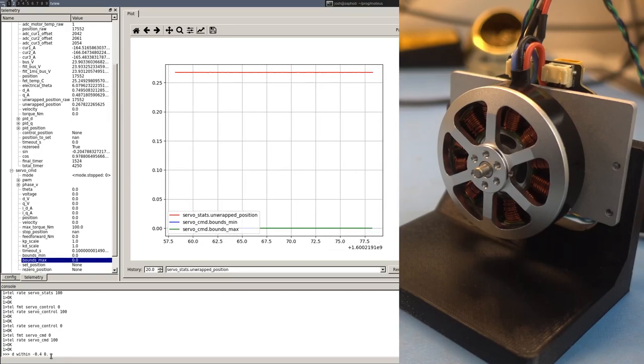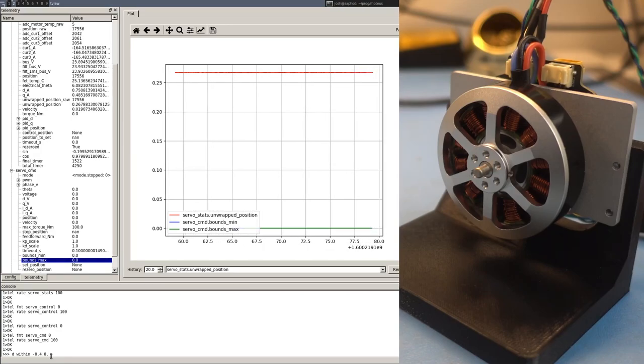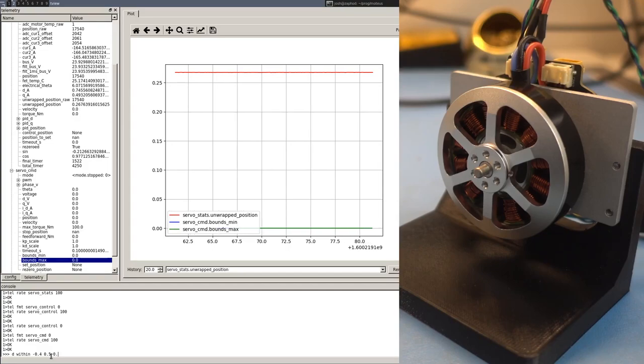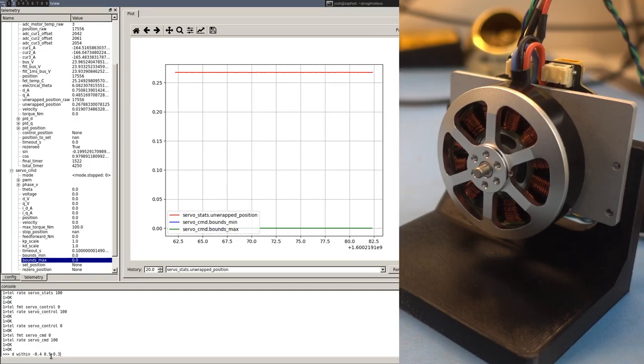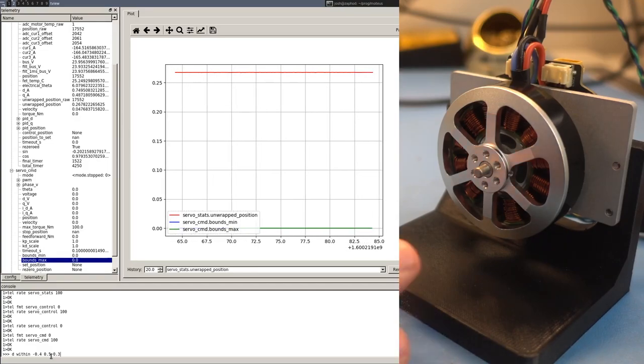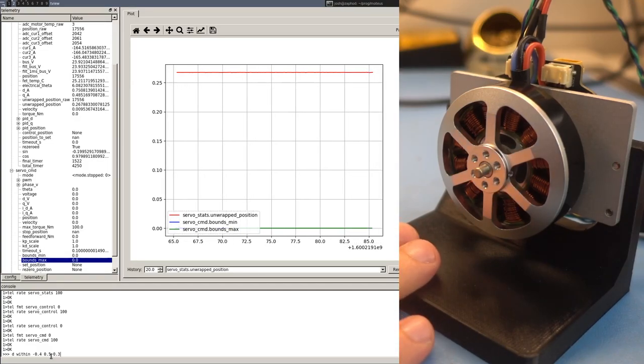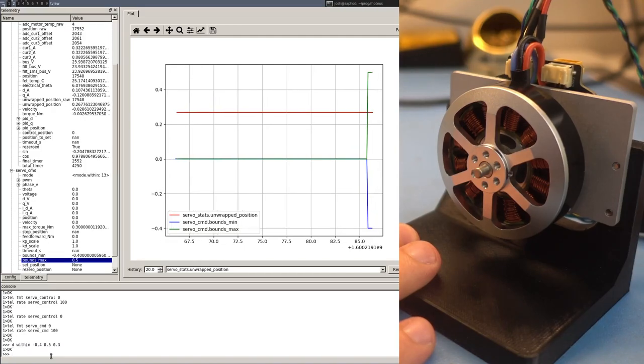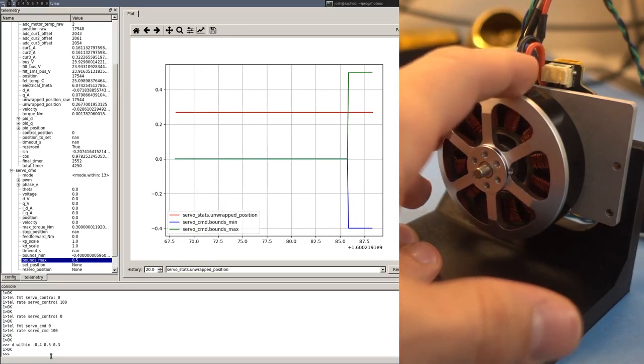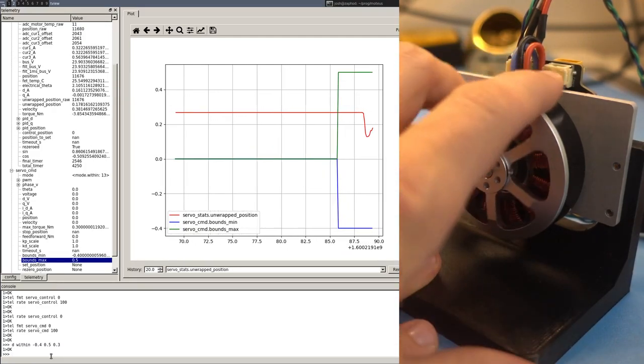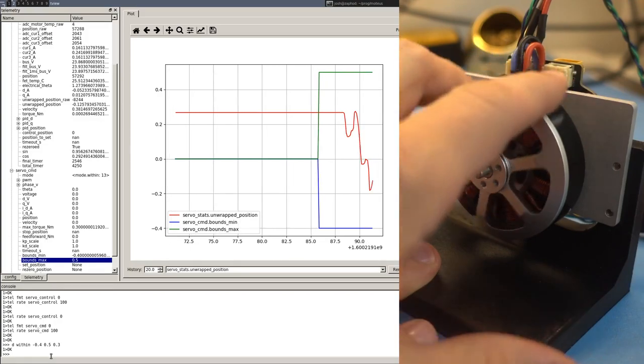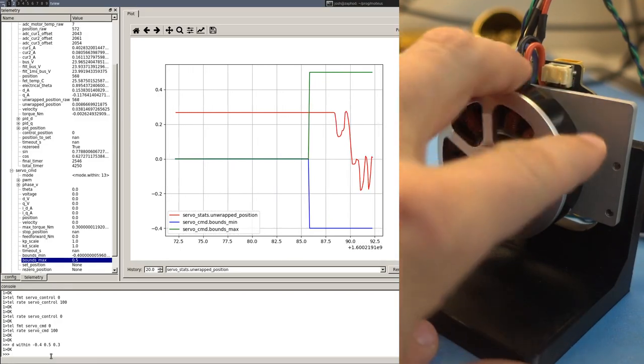So I'll give a lower bound of -0.4, an upper bound of 0.5, and a maximum torque of 0.3 newton meters. And we'll turn that on. And now, as long as we're within those two bounds, there is no torque applied.